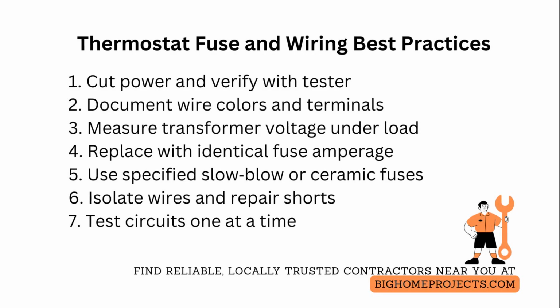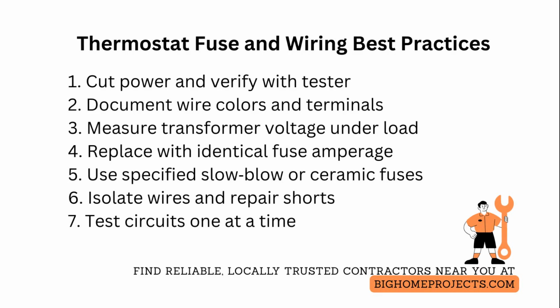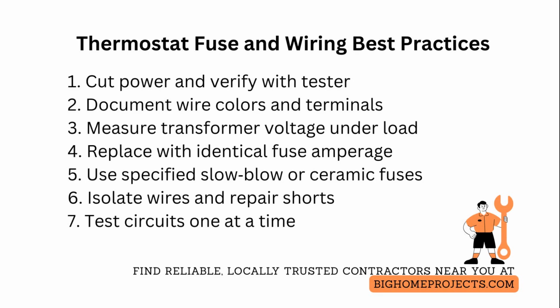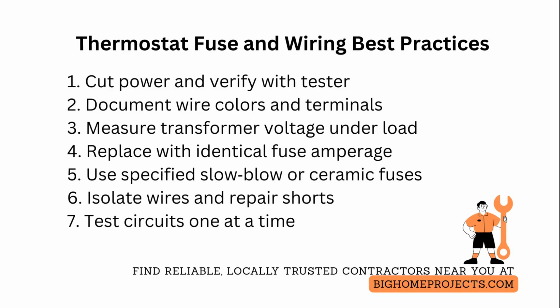Trace the low voltage transformer leads and measure secondary voltage under load to detect a partially shorted transformer that can drop voltage and blow fuses intermittently. If a 3 amp fuse blew, that indicates a low voltage short or wiring error drawing excessive current.